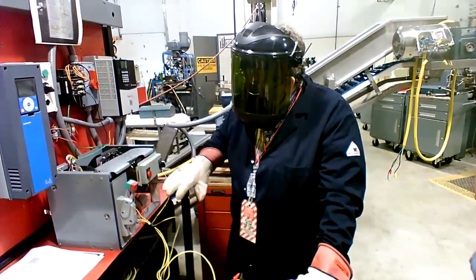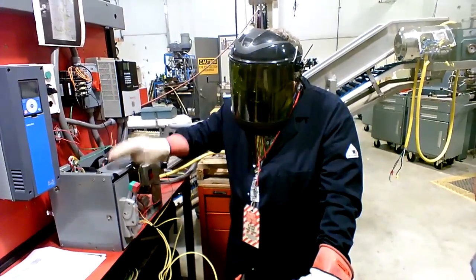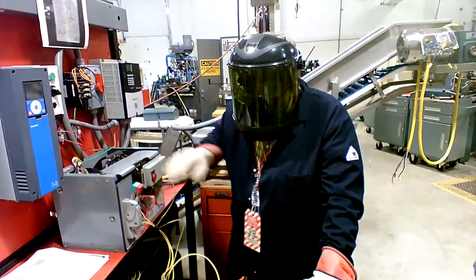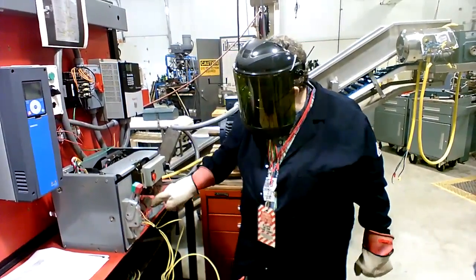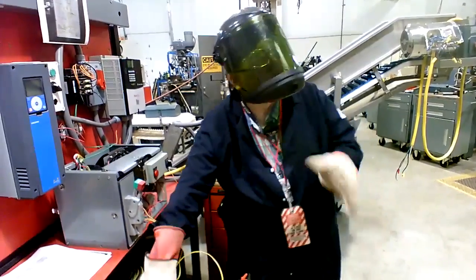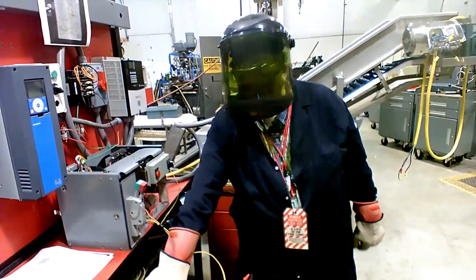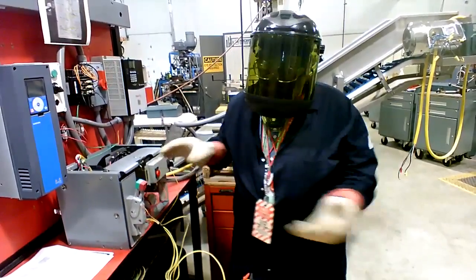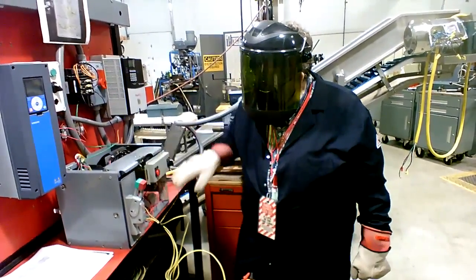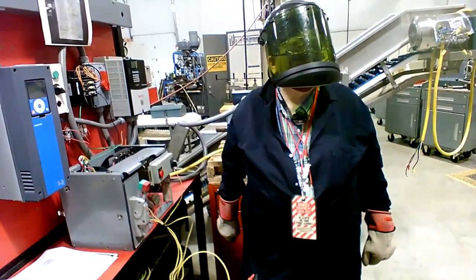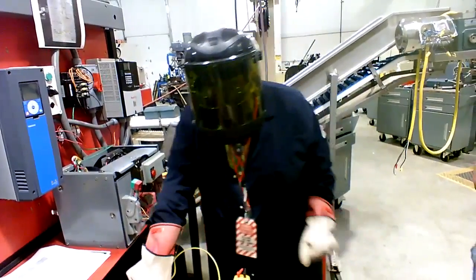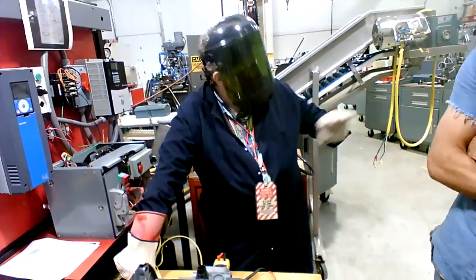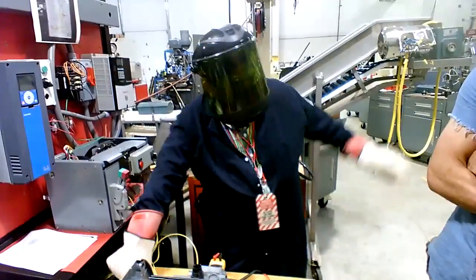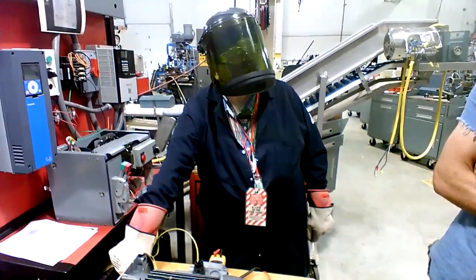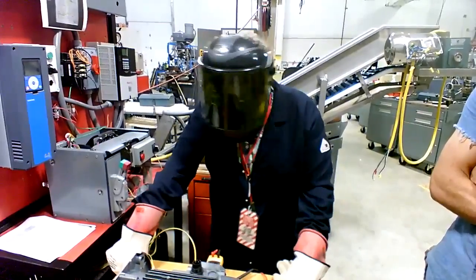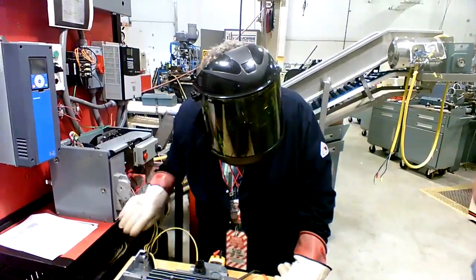And low voltage on a bucket like this could be anywhere from 208 volt to 240 in that range. And if it was 208 volt, it would be 208 leg to leg and 120 leg to ground. That sounds strange, but that's really what it is. So if you're in that low voltage 200 volt range, between 208 and 240, it's 120 leg to ground. In the motor controls class in January, you'll be testing those voltages in both systems, in this system and in the low voltage 240 system. You get some hands-on with that stuff. Okay? We're going to cut this off here, but look away from it.